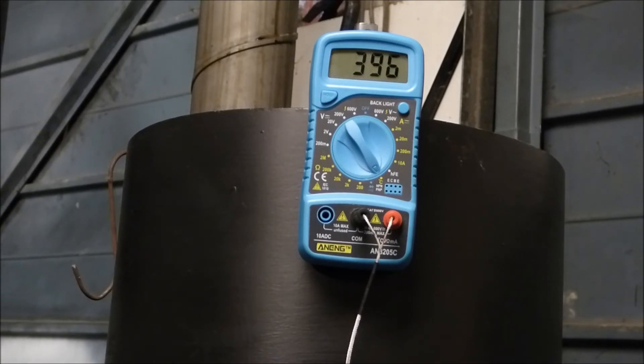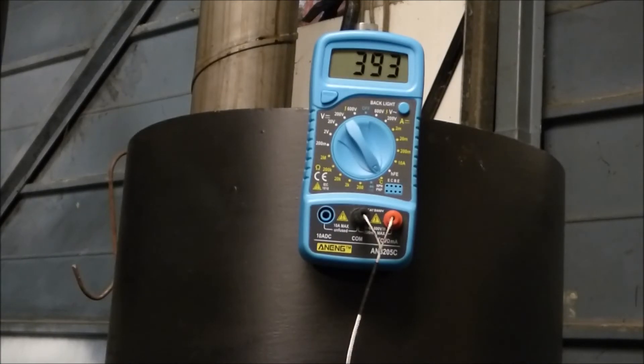And it will take a lot more rads than what I've got on there. That's just for demonstration purposes. And to show you how hot the water, I don't know if you won't be able to see it, but the water in the F and E tank, cold feed and expansion, is steaming, because there's not enough radiators on the system. And the temperature on there, I tell you now, you'll be surprised, in centigrade, is, oh yeah, 46. Yeah, it's just focused. That's on the F and E tank, and that should be cold. So it shows you how much water it's chucking back in the top there to get rid of it. So it's all running quite nicely, really. But you can't, I can't show you the steam coming off the top of the cold feed and expansion tank. Believe me, there is steam coming off.